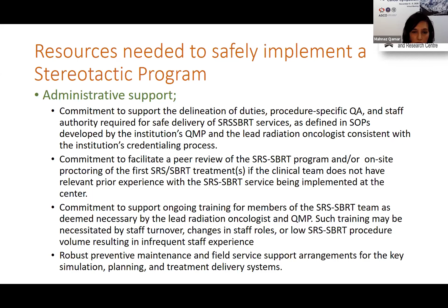Also, because these are really sensitive machines, you need a robust preventive maintenance program and service support. If there's only, let's say, one system commissioned for SRS and SBRT, and there is no backup, then you would want fast service support so that the system is not down for longer than absolutely necessary. So the role of the physicist actually does not start after the machine is installed. It starts well in advance, when the decision of selecting such a modality is being made. The physicist who has had experience must be involved in the process of facility design and equipment selection and specifications, so that nothing is missed.